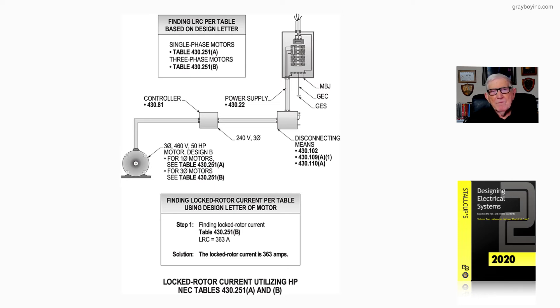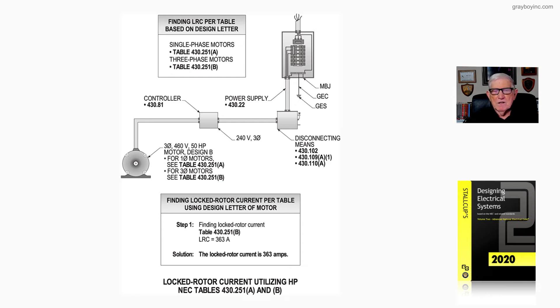In step 1, we apply the design letter B and refer to table 430.251, as instructed from 430.7A9 on around page 310 in the NEC. Based upon design B in step 1 of the illustration, we find 363 amps.